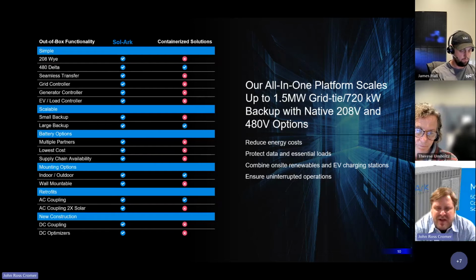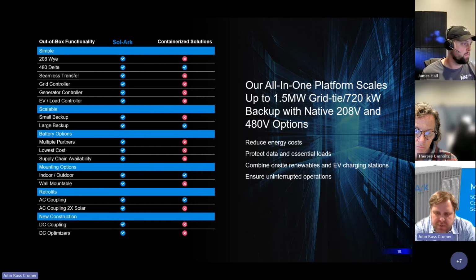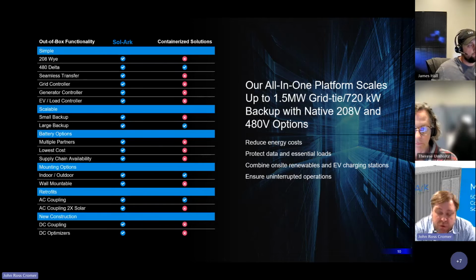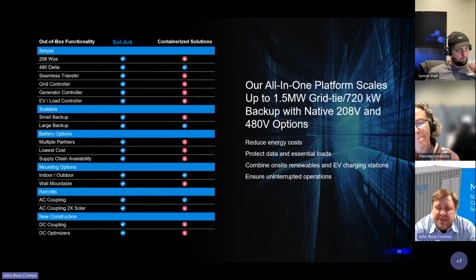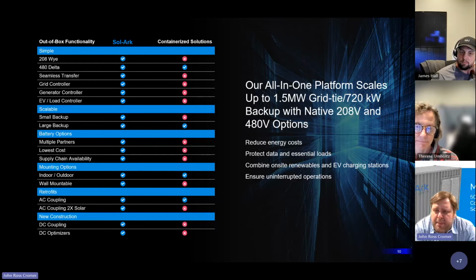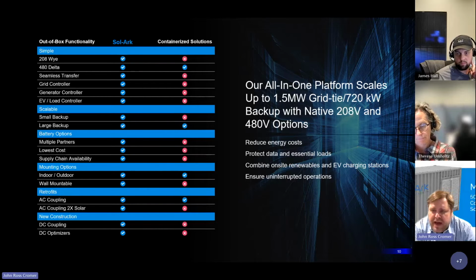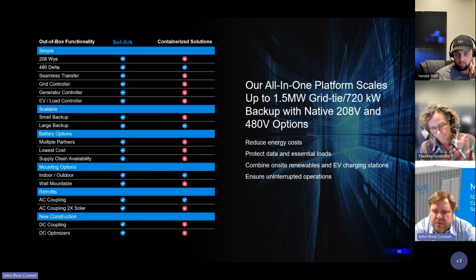Containerized solution, there's a rather large buy-in cost to get to. You have to buy a megawatt hour worth of storage. So this is a good 30 kilowatt hour or 40 kilowatt hour, 60 kilowatt hour as your minimum starting point. And it's very scalable, up to 1.5 megawatt AC coupled, 720 kW backup on 480.